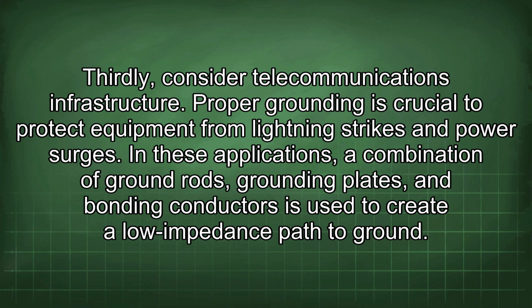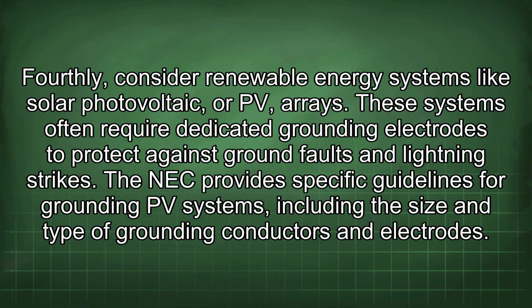Thirdly, consider telecommunications infrastructure. Proper grounding is crucial to protect equipment from lightning strikes and power surges. In these applications, a combination of ground rods, grounding plates, and bonding conductors is used to create a low impedance path to ground. Fourthly, consider renewable energy systems like solar photovoltaic or PV arrays. These systems often require dedicated grounding electrodes to protect against ground faults and lightning strikes. The NEC provides specific guidelines for grounding PV systems, including the size and type of grounding conductors and electrodes.